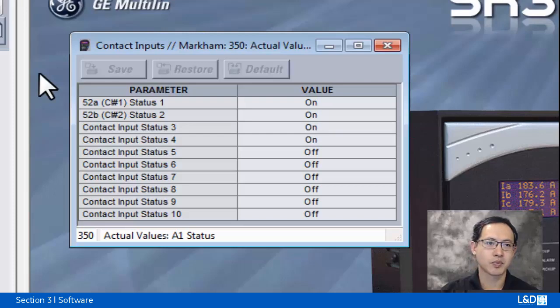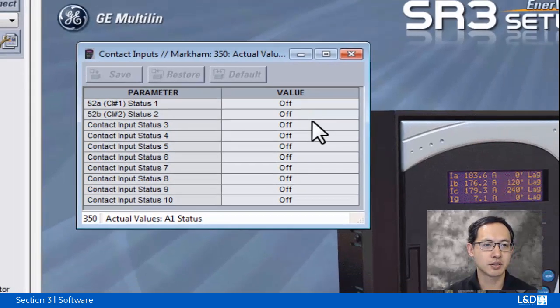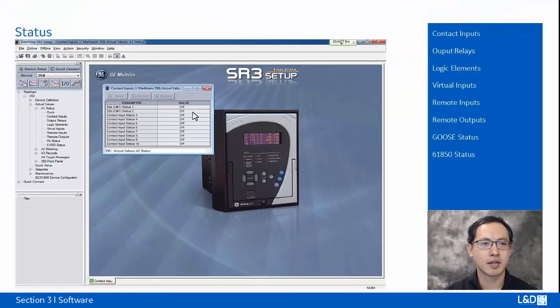We can see the status changed in the contact input 1. Then we can turn them off one by one. So you can see the status changed. It's the same way we can verify the status for the output relays, logic inputs, virtual inputs, and remote inputs outputs in the following modules.